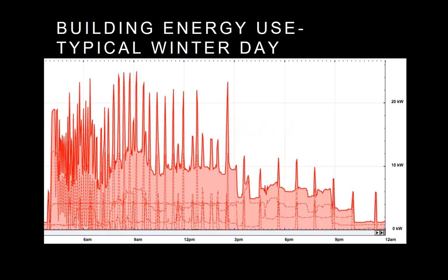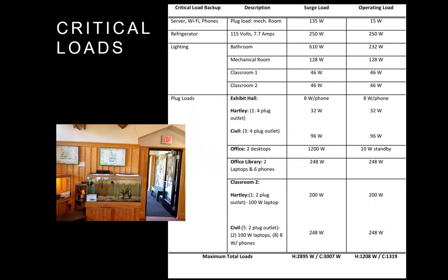As you can see, some very spiky graphs. One thing we learned in this project is that they have a water heater disconnected from the ground source heat pump, because that heat pump failed, and it's causing these demand spikes. That's just one example of something we found and how we used it to select the battery.